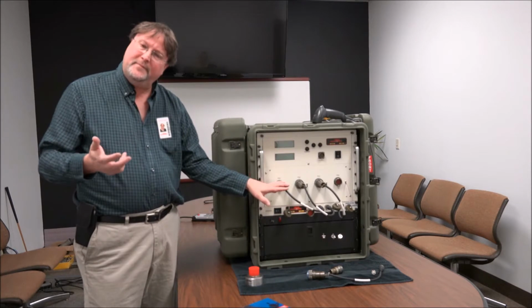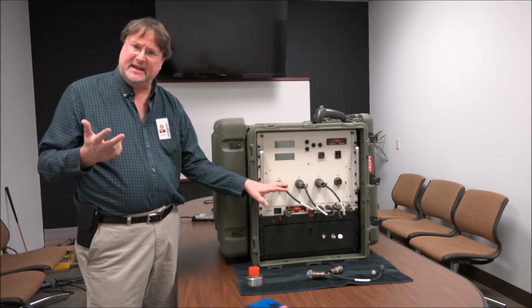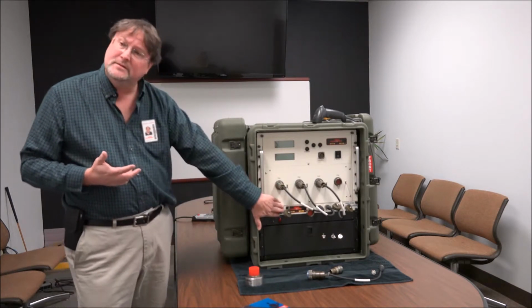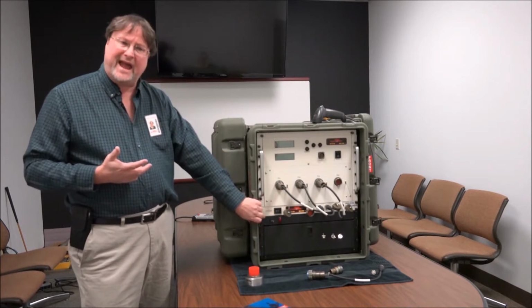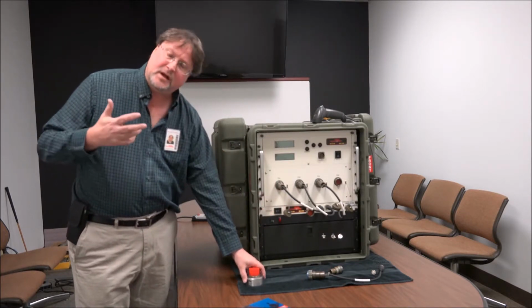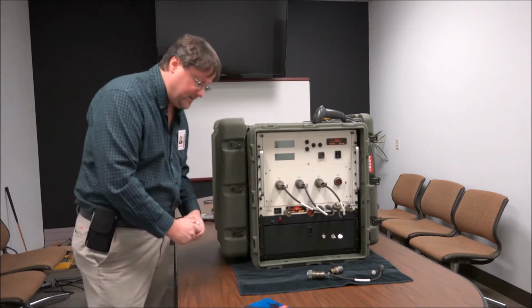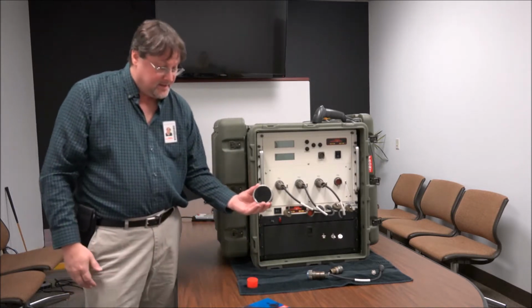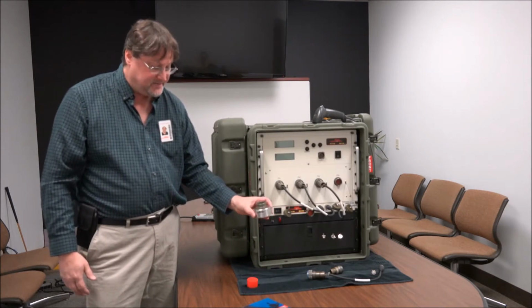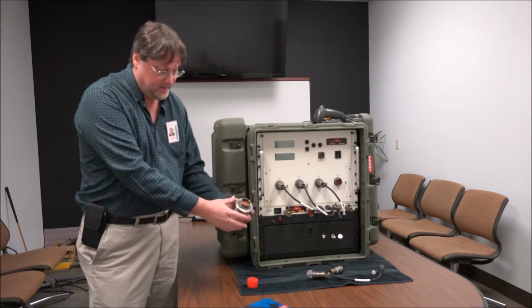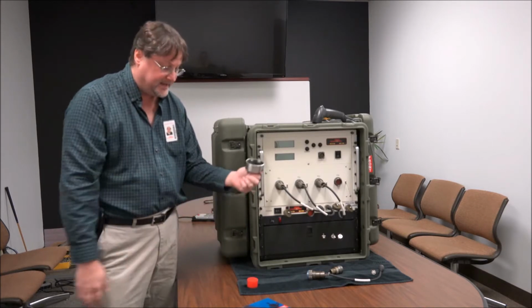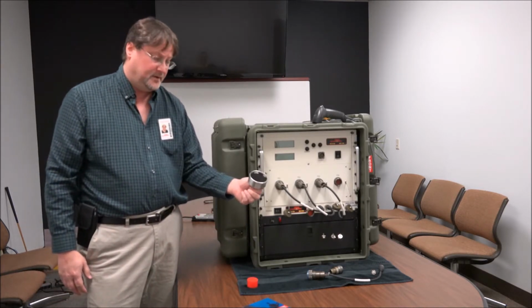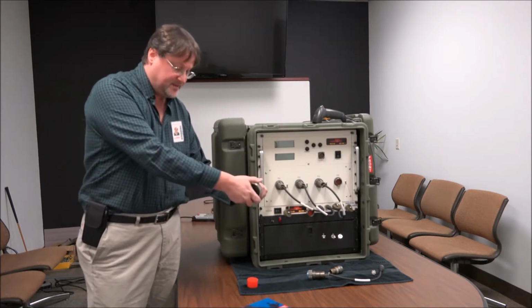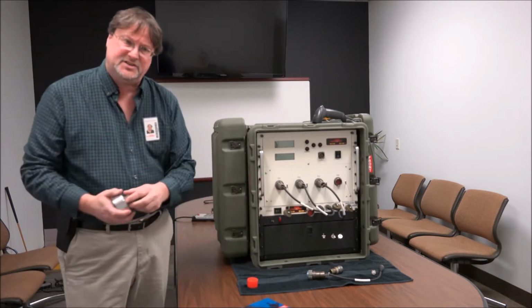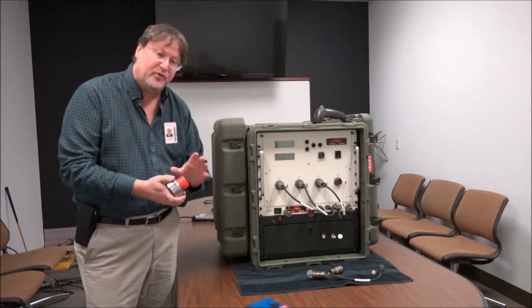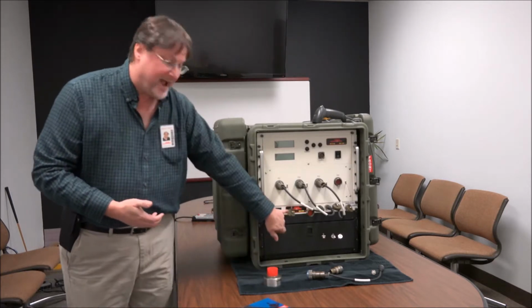The weapon simulator can be made in 2 different formats. It can be a rack attachment, placed in the same rack as the tester, or if you have a limited number of circuit paths, it can be made as a plug arrangement. This mounts to the end of the cable that attaches to your weapon, protecting the cable end and providing loads that emulate the weapon. When you go to use the weapon, you simply unscrew it, bring the cable out, and attach it to your weapon. So there are 2 formats: a plug format and a rack mount format.